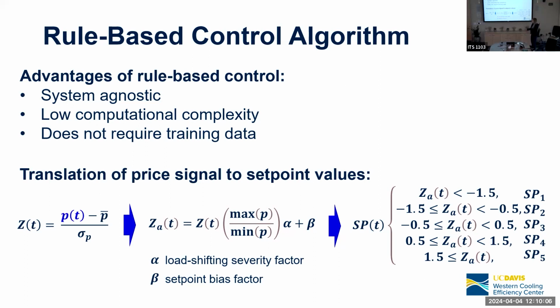The way we're taking in a price signal and turning it into set points is with the Z-score. That tells you where in a normal distribution a particular price falls, how far from the mean. We calculate a Z-score and then adjust it by finding the ratio of max to min price signal prices, then multiply that by a load shifting severity factor to amplify or decrease the peaks in that price signal.